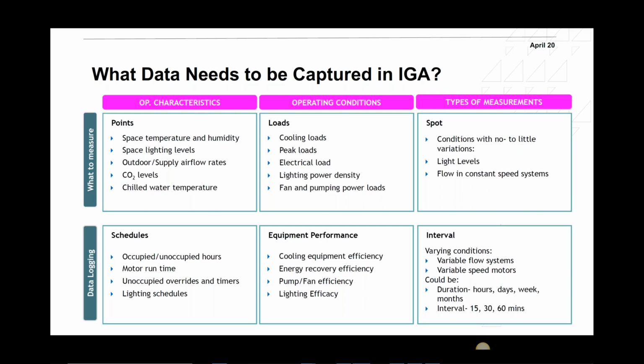Data logging, I would do data logging to check the schedules, when motors turn on and off, or lighting. Equipment performance, if I want to check the kilowatt per ton for a chiller, I need to put a BTU meter to check the cooling load, and I would need to put maybe a power analyzer on the electrical side to see what the kilowatt per ton is. Compare that to the nameplate to see if there's any derating or how the equipment is being used.